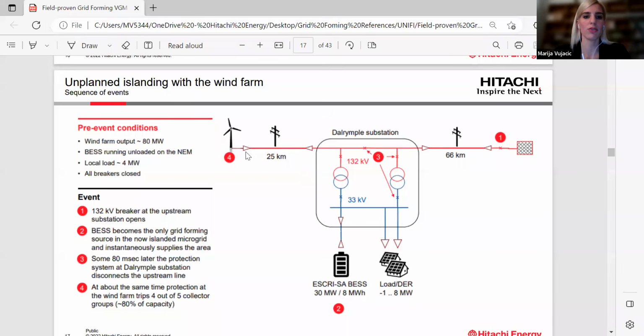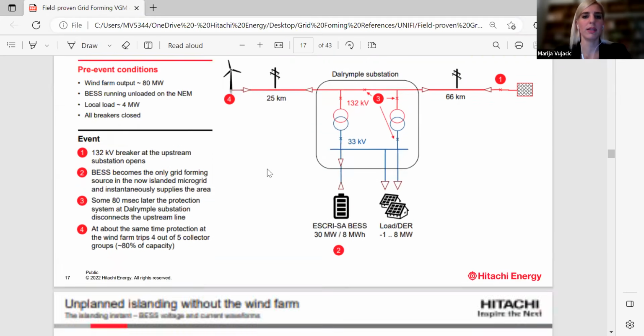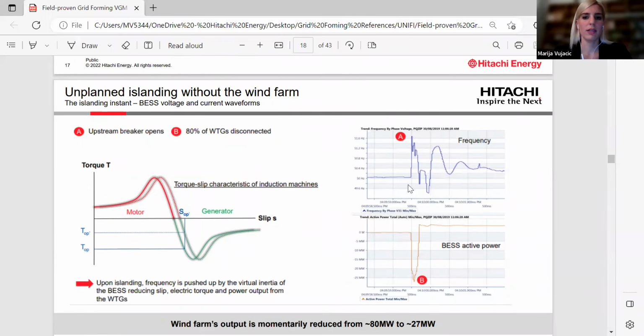But at this moment, we also had the wind farm connected to the network. Some 80 milliseconds later, the protection system at the substation disconnected the upstream line, and at that moment 4 out of 5 collector groups inside the wind farm tripped, reducing the output of the wind farm by 80%, and you will see that on the next slide. As you can see here, as the frequency increased, the battery energy storage started charging. At that exact moment, the power of the wind farm was reduced to 20% of its nominal rating. So it was around 27 megawatts, which was below the power rating of the battery energy storage system. So the battery system did not trip.